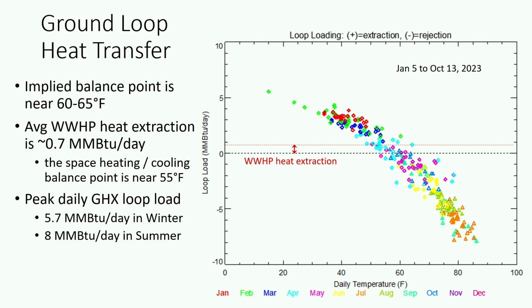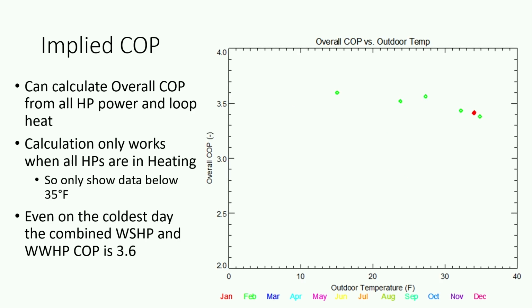Our peak winter load was about 5.7 million BTUs per day, and 8 million BTUs in the summer. So still more heat rejection in the summer, but they weren't too far apart. Because I had these BTU meters on the loop, and I knew the heat extraction, the heat rejection, and what the heat pumps use, I can infer a heat pump efficiency for space conditioning. I can only do it when I'm pretty sure there's no simultaneous heating and cooling. It implied that even on the coldest day, the combined efficiency for the water heating system and the space conditioning system was about 3.6 overall.